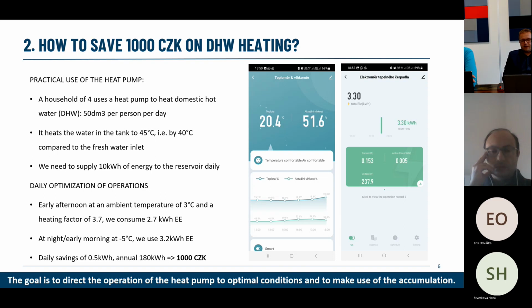And just an illustration, if you think of a household that has 4 inhabitants, and you consider that the heat pump provides the domestic hot water. If you assume each person consumes 50 liters per day, the total requirement would be 200 liters per day for that household. And you assume that the water needs to be heated up from the freshwater inlet at 5 degrees C to 45. That means the temperature gradient is 40 degrees C. You would have to deliver roughly 10 kilowatt hours of energy to the domestic hot water reservoir every day.